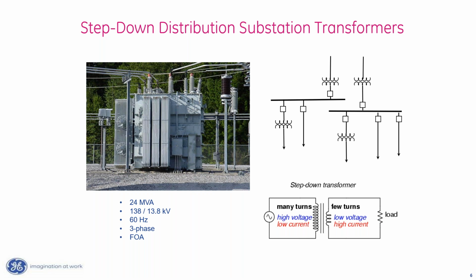But also in the step-down, it'll block the zero sequence currents from the transmission system, just like it blocks the zero sequence currents from the generating station. So I don't need to coordinate my ground protection for my transmission system with the ground protection out on the distribution system and worry about false tripping my transmission system for every single squirrel out there that we're going to electrocute.